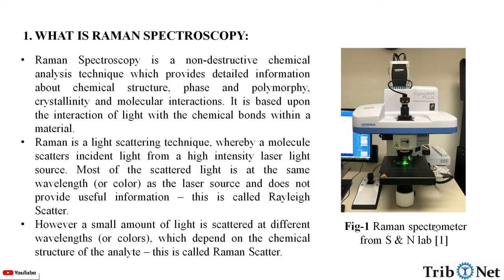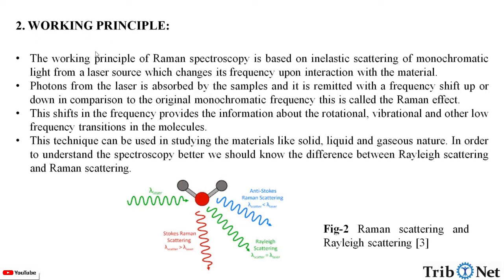Here in this figure we can see the Raman spectroscopy from S & N lab. The working principle of Raman spectroscopy is based on inelastic scattering of monochromatic light from a laser source, which changes its frequency upon interaction with the material. Photons from the laser are absorbed by the sample and remitted with a frequency shift up or down in comparison to the original monochromatic frequency — this is the Raman effect. This shift in frequency provides information about the rotational, vibrational, and other low frequency transitions in the molecules.